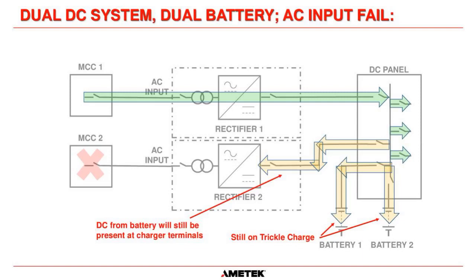So if you lose the AC input to one of the parallel chargers, what's going to happen is charger 1 will just carry on going regardless, supplying all the current to the DC panel, and it will keep both batteries charged. But do remember that there is a back feed to the other charger if you need to go in and find out what's wrong with the system. Okay? Hopefully that makes sense.